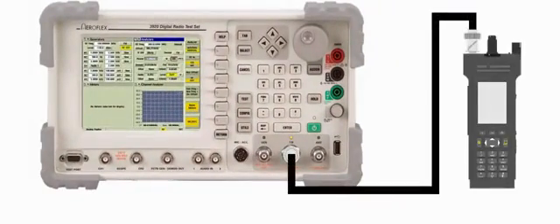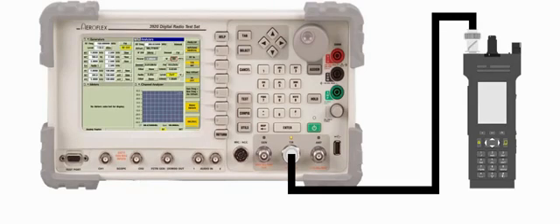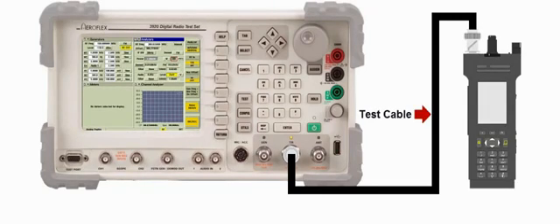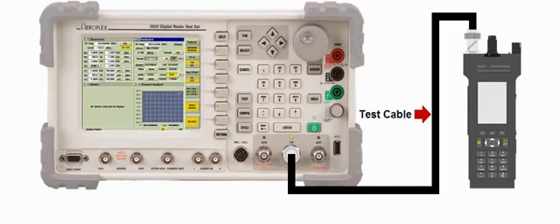We begin this video with the standard connection used to measure transmitter power. A coaxial test cable connects the radio's antenna port to the instrument's TR port. When the radio is keyed, the power is measured by the broadband power meter.